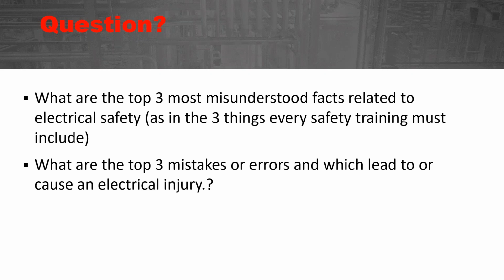No. You've got to live-dead-live: test the tester, test for the absence of voltage, and test the tester again. That last step, test the tester again, is one of the things that a lot of people miss in the actual hands-on training or in the field, even the field work audit that is a requirement in 70E.